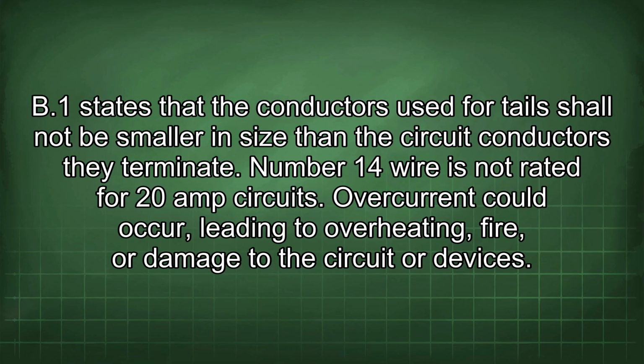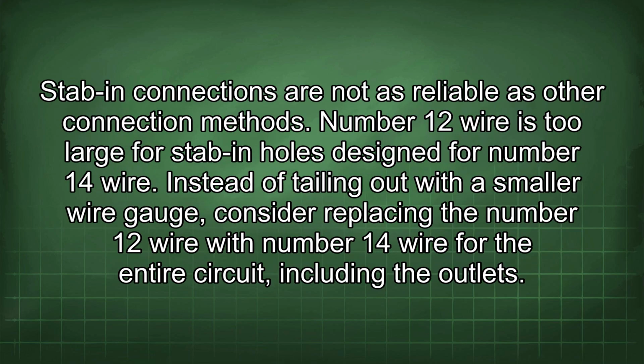Overcurrent could occur, leading to overheating, fire, or damage to the circuit or devices. Stab-in connections are not as reliable as other connection methods. Number 12 wire is too large for stab-in holes designed for number 14 wire. Instead of tailing out with a smaller wire gauge, consider replacing the number 12 wire with number 14 wire for the entire circuit, including the outlets.